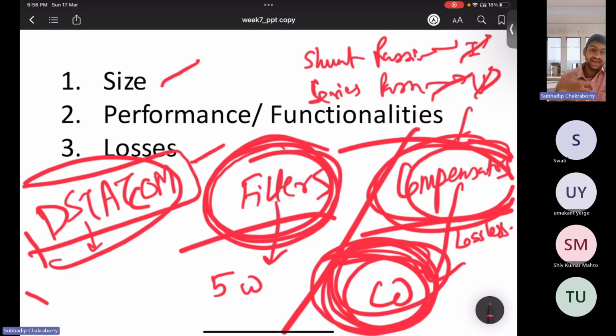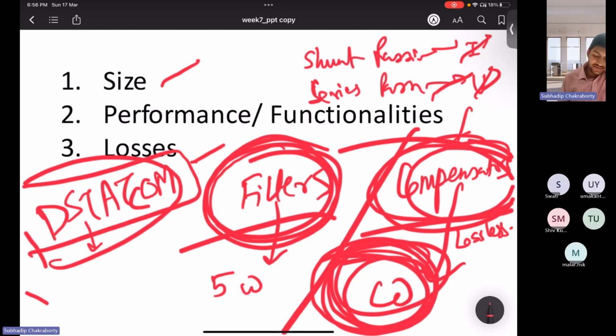So the filters completely extract that harmonic component, but the compensators compensate for the harmonic component. They don't eliminate it. Filters can be thought of as completely eliminating it by providing either a very low drop across the series path for that particular harmonic component, or low impedance in the shunt path for the current to flow during current quality problems. For a voltage quality problem due to a particular harmonic component, you need the voltage drop for that harmonic component to be low. You design some filters such that, in the series path, the voltage drop due to that particular harmonic component is the least, so that it does not appear at the PCC point, and the others just pass.